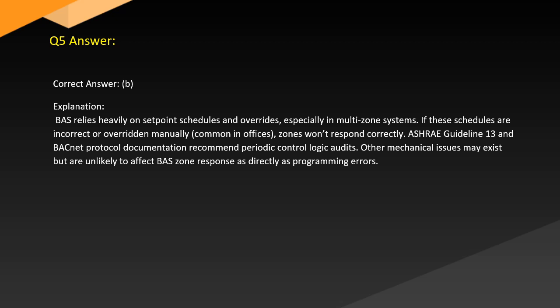Answer. Correct answer, B. Explanation. BAS relies heavily on setpoint schedules and overrides, especially in multi-zone systems. If these schedules are incorrect or overridden manually, common in offices, zones won't respond correctly. ASHRAE Guideline 13 and BACnet protocol documentation recommend periodic control logic audits. Other mechanical issues may exist, but are unlikely to affect BAS zone responses as directly as programming errors.